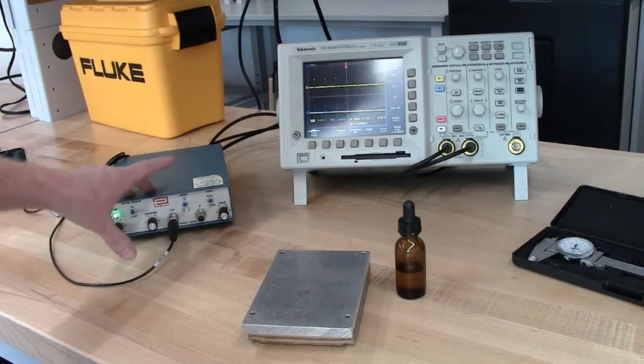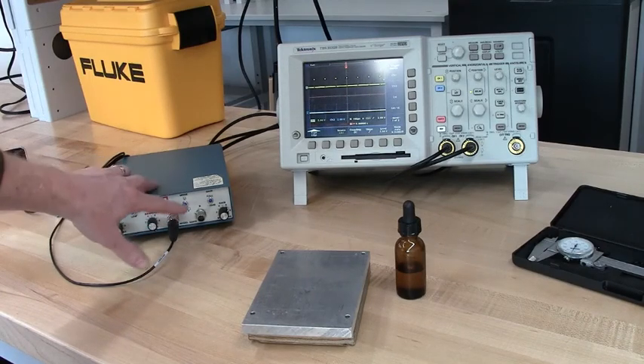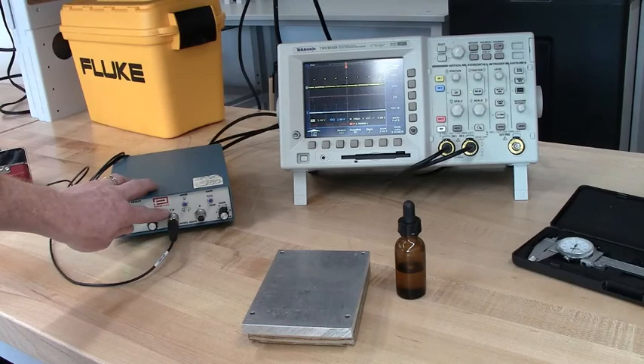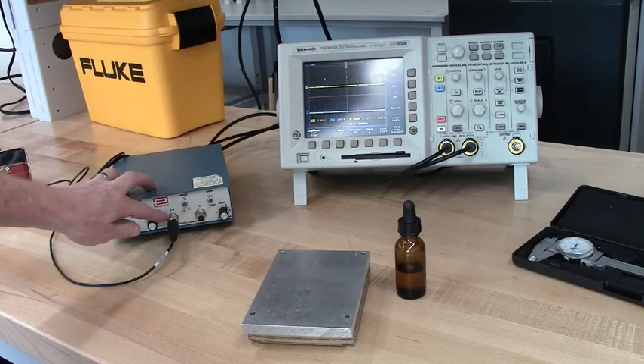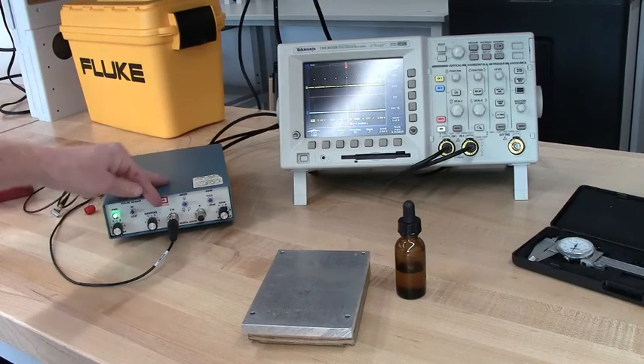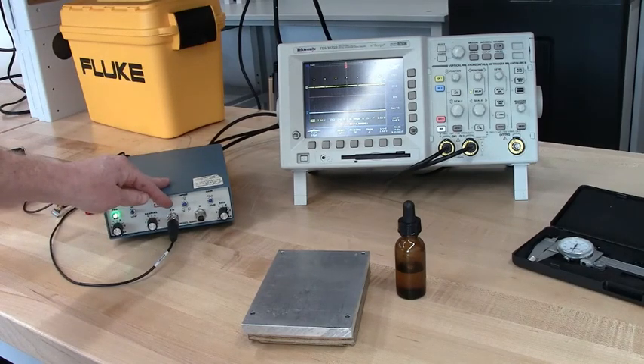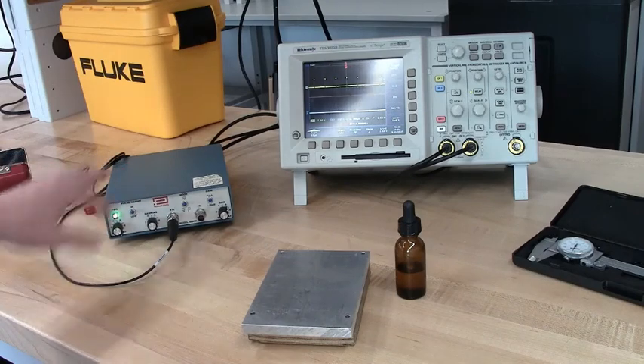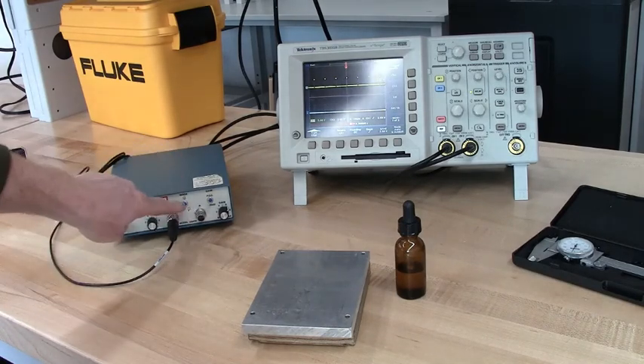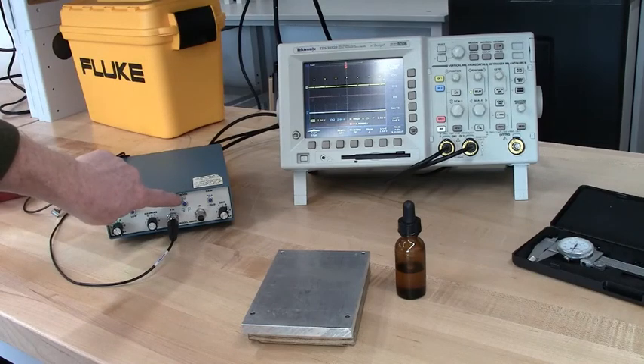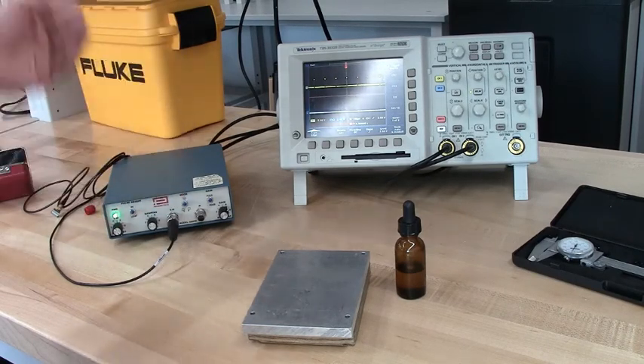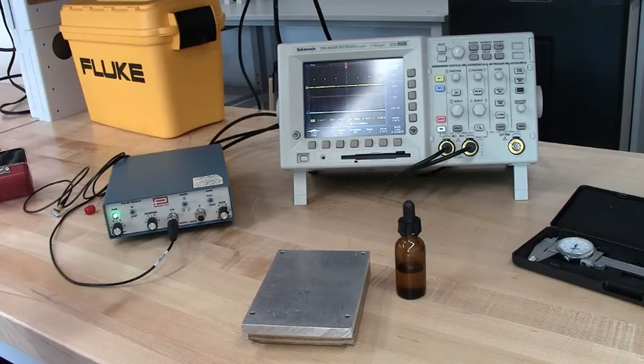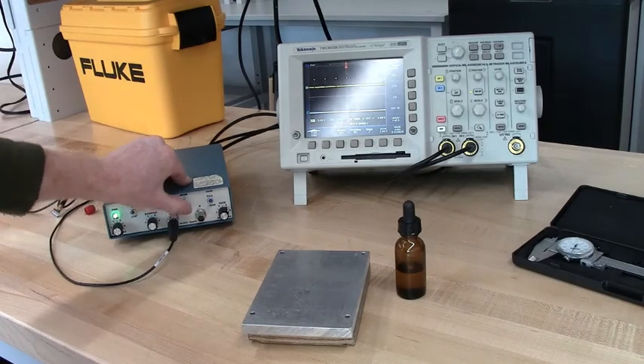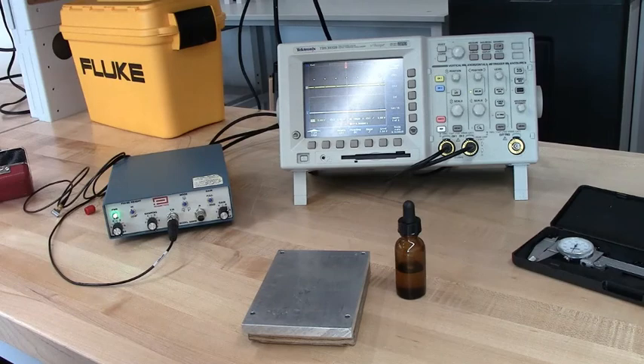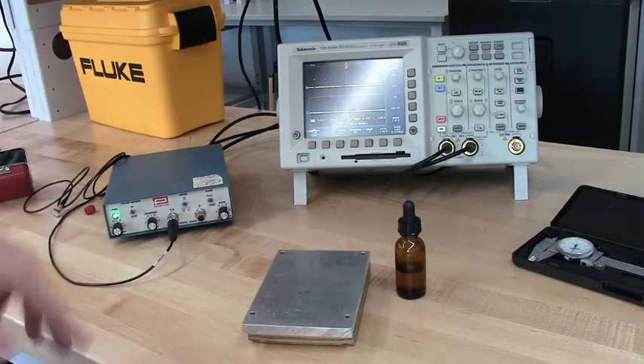The one last setting I wanted to show on here was this mode switch. Here we're connected to this coax that says T/R. The T is for transmit, R is for receive. And when we're in this position up here, you see the little transducer with an arrow that goes up and down, and it's sitting on what you would be measuring. So when you're in this setting and you're plugged into here, you have a transducer that is transmitting and receiving.